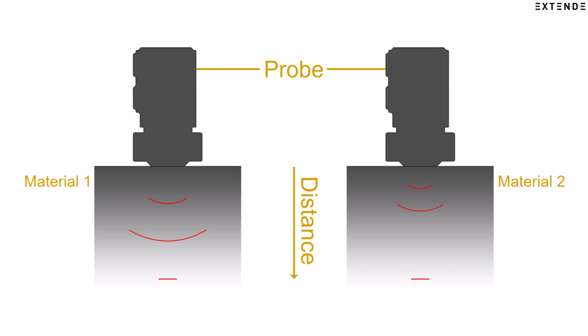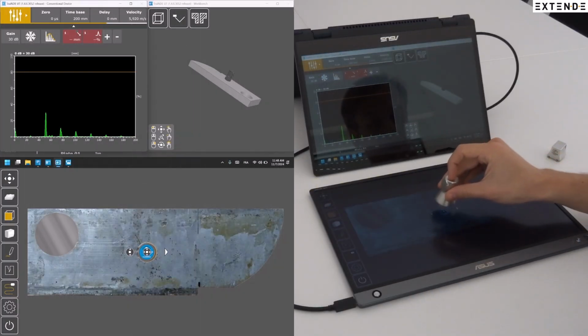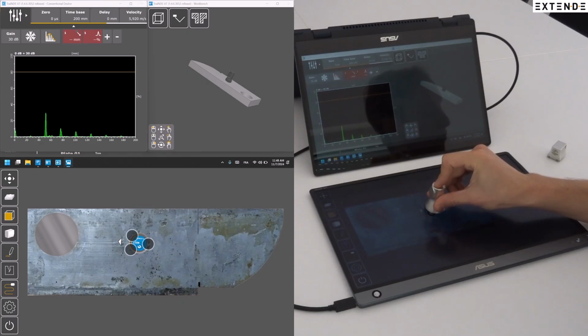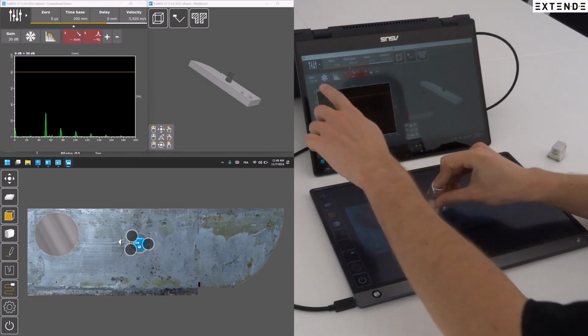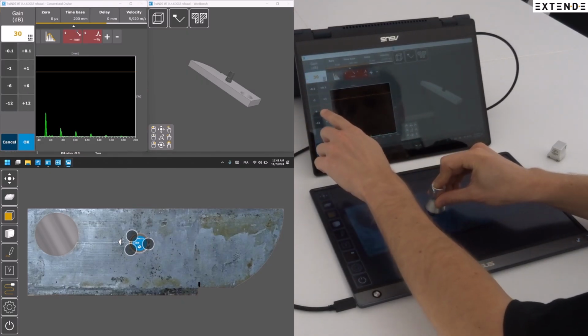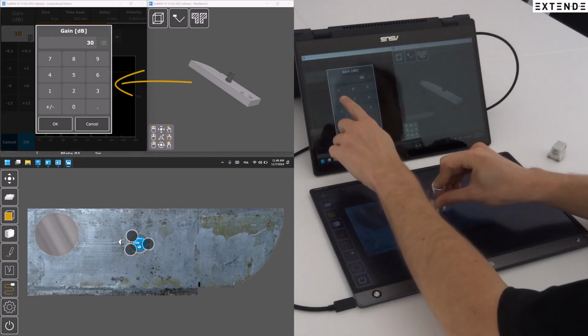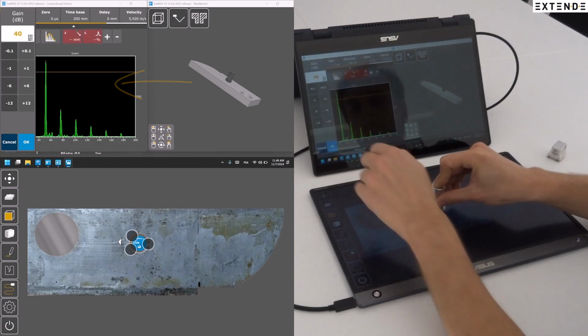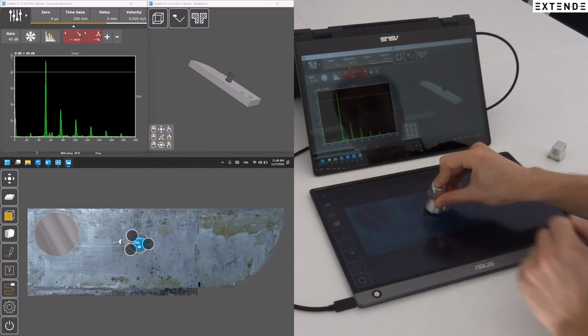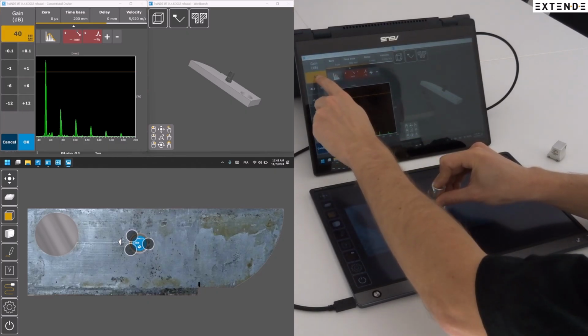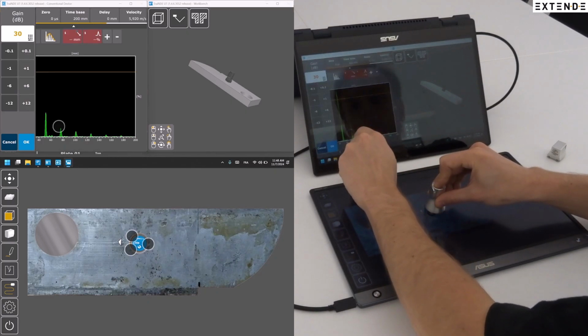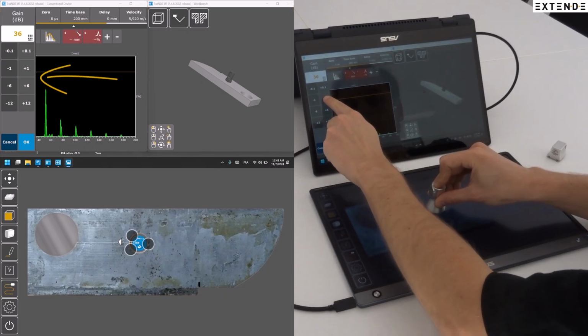The ultrasonic wave travels within the specimen at a velocity depending mainly on the material, but also on environmental conditions. The velocity calibration ensures the measurement of proper distances. Ensure the dummy probe is placed approximately at the center of the front face of the V1 block. Set the gain to 40 decibels, either with the calculator or by clicking on the plus or minus buttons.